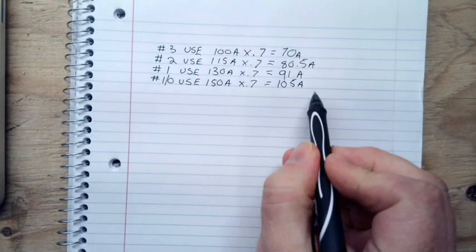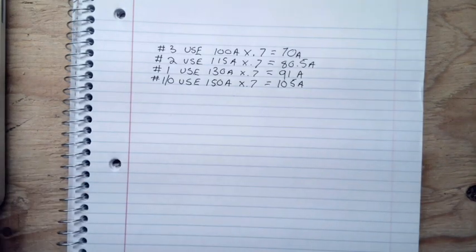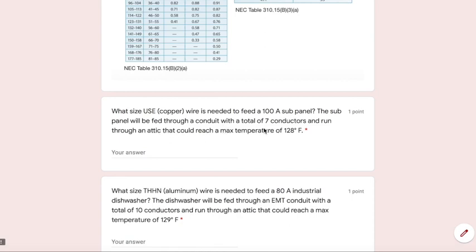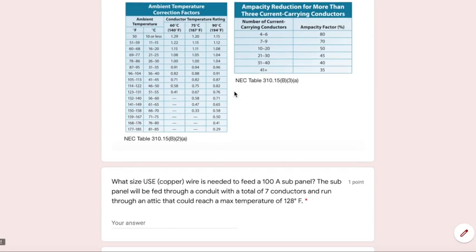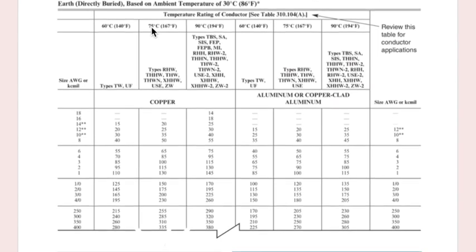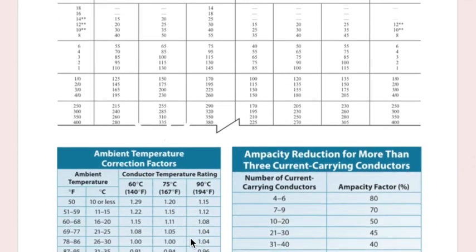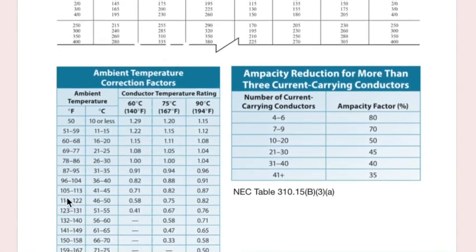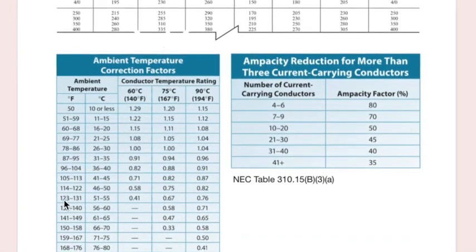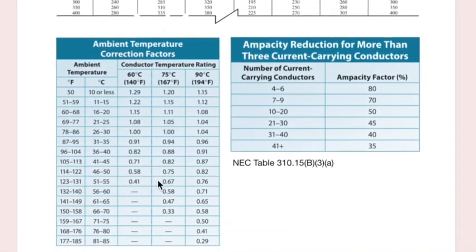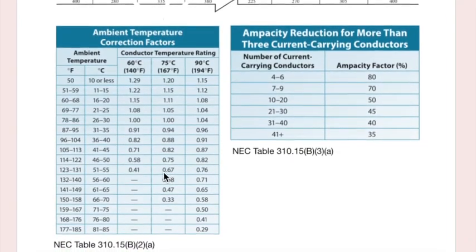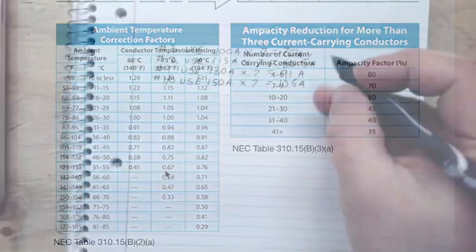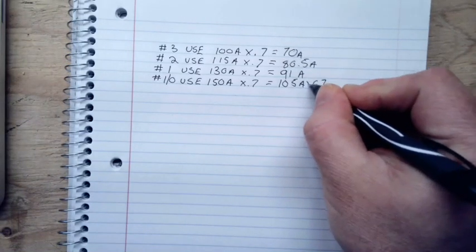So we're good adjusting for that heat, but now we still got to find that correction factor because I went ahead and said that we're going to be running through an attic that could reach 128 degrees. So now we need to take this 105 that we found off the one-ought that we think is good and figure out 128 degrees. We're dealing with U.S.E. Let's find that first. So I got U.S.E. is in the 75-degree chart. So I'm going to come down to the 75 chart. And I believe we said we're at 128. So I'm going to look for 128. 128 falls between 123 and 131.